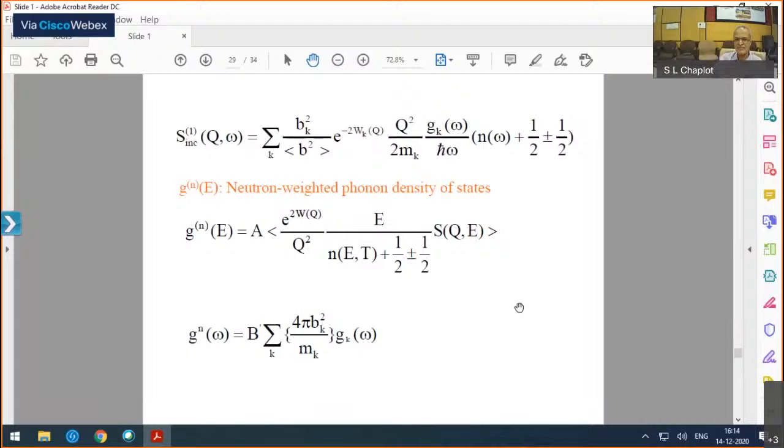Okay, it's only maybe the Debye-Waller factor or some standard instrument parameters, which can be more easily corrected. So, vanadium is often used as a standard sample for calibration of the instrument. And with respect to that, we can see how these intensity corrections can then be made, coming from all kinds of factors.